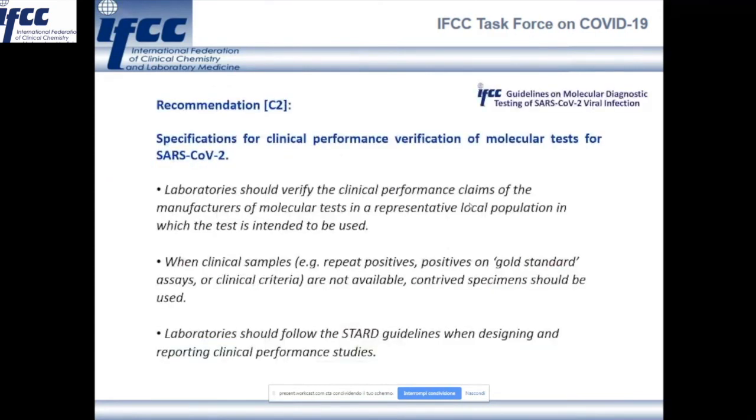As specifically concerned the specification for clinical performance verification of molecular tests for SARS-CoV-2, the IFCC recommends that laboratories should always verify the clinical performance claims of the manufacturers of molecular tests in a representative local population where the test will be used. When clinical samples are unavailable, and this specifically refers to repeat positives, positive or gold standard assays, or clinical criteria, contrived specimens shall be available and used. Finally, all clinical laboratories shall prefer to follow the STARD guidelines when designing and reporting clinical performance studies.